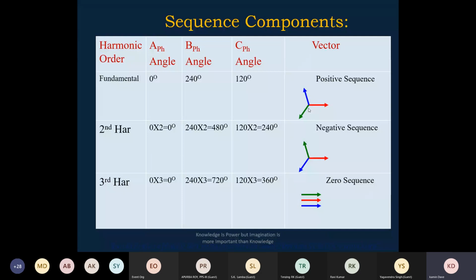So when we say there is a ground fault or zero sequence component, then we can say the third harmonic is present during a phase to ground fault. Normally we use these terms in many such fault conditions, and even in lightning arrestor leakage measurement, we can say third harmonic measurement. Some manufacturers say third harmonic resistive component measurement, which means they segregate the capacitive component and the resistive component. That is again a phasor, the third harmonic phasor, and then they calculate the real component plus the imaginary component.